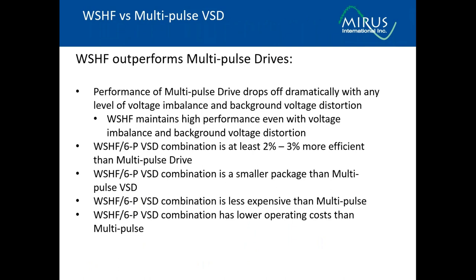Let's take a few minutes also to look at one of the other passive options for treatment of harmonics, which is multi-pulse systems. One of the issues with multi-pulse is that performance drops off dramatically when there's voltage imbalance or background voltage distortion. Whereas with a wide spectrum harmonic filter, the performance maintains itself quite well, even in those severe environments. There's higher efficiency with a wide spectrum harmonic filter than multi-pulse drives, because the multi-pulse drives require transformers to do the phase shifting, which introduce additional losses. The package is typically smaller, less expensive, and because of the reduction in losses, has a lower operating cost associated with it.